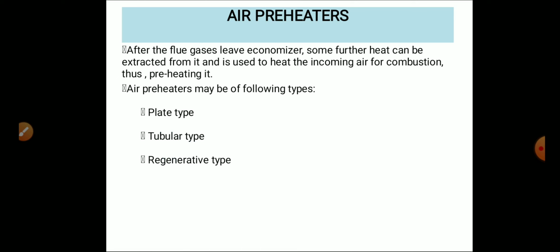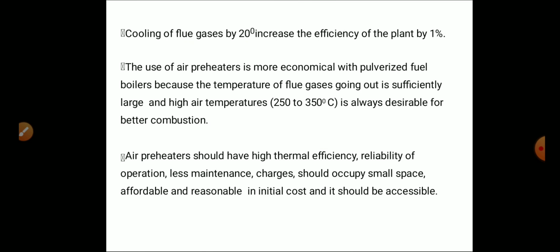Air preheaters may be of the following types: plate type, tubular type, regenerative type. Cooling of flue gases by 20 degrees increases the efficiency of the plant by 1%.